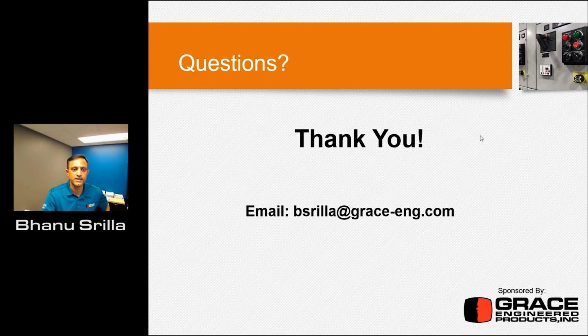It's a lot of information. I mean, 70E gives the safety work practices, but 70B gives you the complete guidance on what those maintenance requirements are. And that has detailed information for every foreseeable component of your electrical systems, from your switchgear, MCCs, breakers, transformers, bus ducts, SCADA systems. Yeah, it's great information. You can just read that.